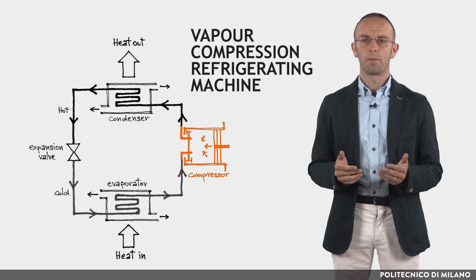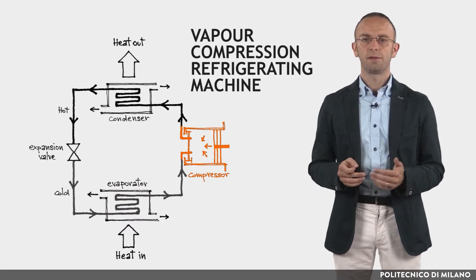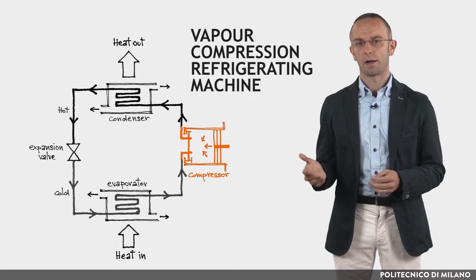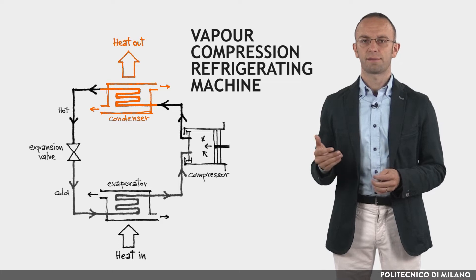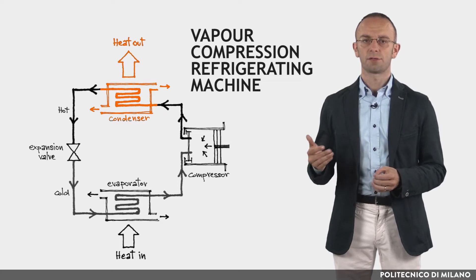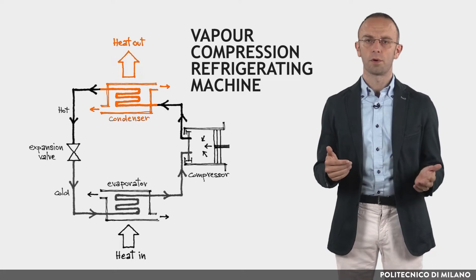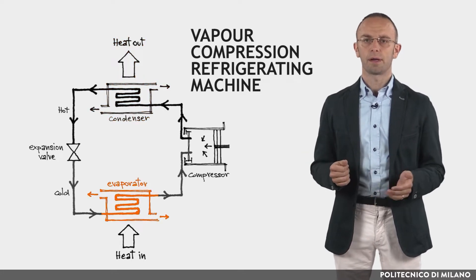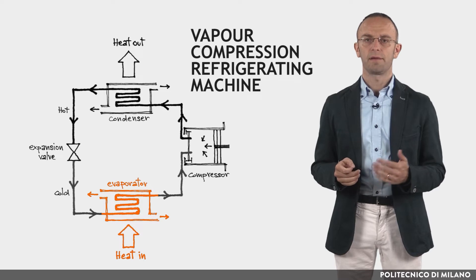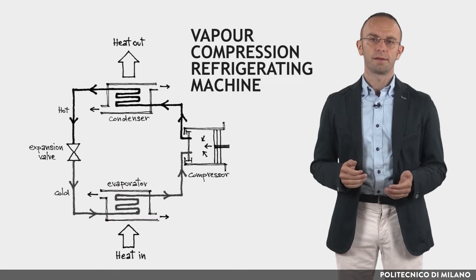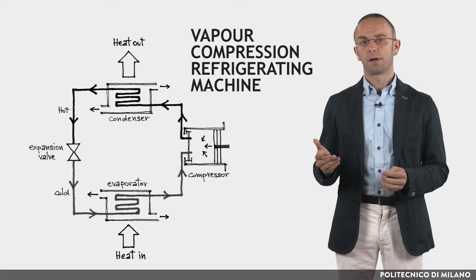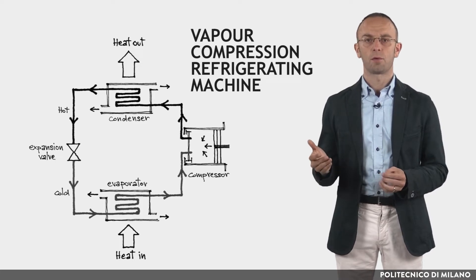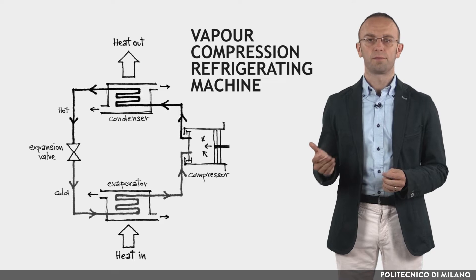The refrigerant enters the compressor as a vapor and is compressed to a higher pressure and consequent higher temperature. In the condenser, the circulating refrigerant rejects heat from the system, and the rejected heat is carried away by either water or air. In the evaporator, heat is subtracted from the environment by the evaporation of the liquid part of the cooled refrigerant mixture. The greater the temperature difference between condenser and evaporator, the greater the required pressure difference, and consequently more energy is needed to compress the fluid.